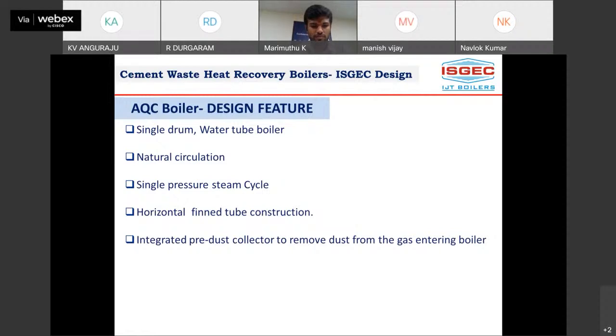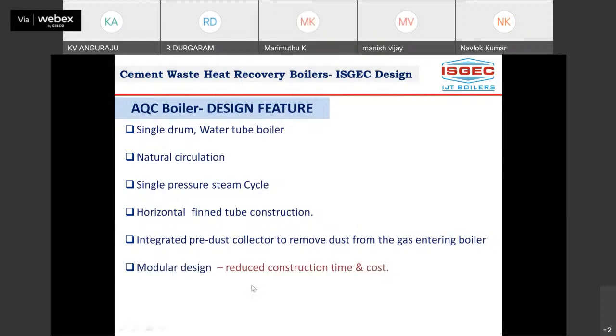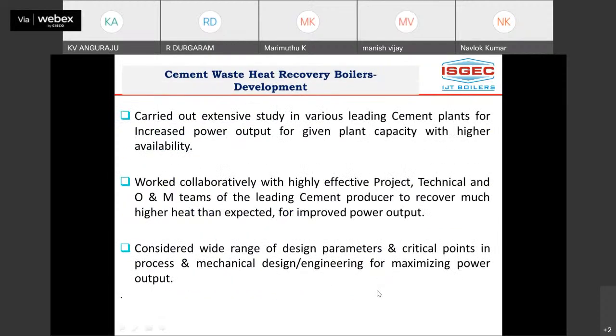For this, one is the pre-dust collector and its internal design, along with CFD modeling. Then followed by sacrificial tubes, then your pitch arrangement, support arrangement, and baffling at the end of it. That means the plain tube surfaces and bends, how they are protected, is very important in the AQC boiler. Again, it's a modular design for quicker erection, then velocity to prevent erosion.